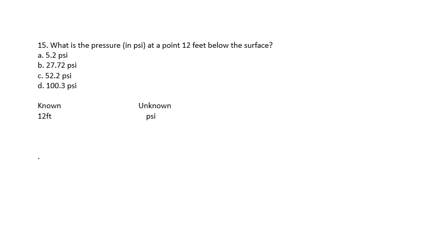If you know your conversions, 1 foot of water head is equal to 0.433 PSI, or 1 PSI is equal to 2.31 foot of water head. You can use either one of these interchangeably. We're going to rearrange them so that everything cancels out. So you have the 0.433 PSI over 1 foot, so you're going to multiply that, and then you have 1 PSI over 2.31 feet, so that'll end up being division, so things cancel.